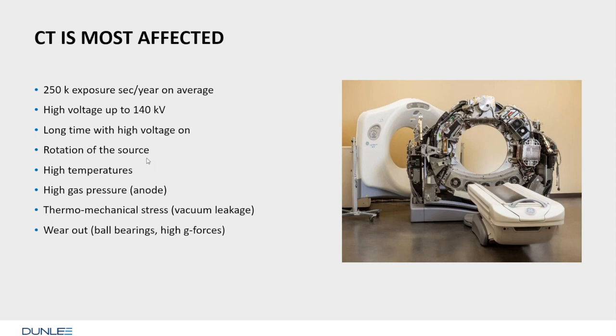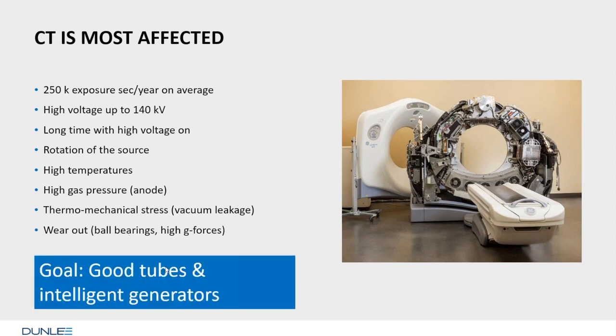We will see that. The temperatures are pretty high. CT operates some tubes to the edge. The gas pressure created by the anode may be pretty high compared to other modalities. And there may be thermomechanical stress. If you operate a tube with 30, 40, 50 patients per day, it heats and cools, so there may be thermomechanical stress and even vacuum leakage that can occur. And there's wear out. Ball bearings at high G forces and the anode also, these things are wearing out and create particles. So what we need is good tubes, stable with respect to performance. And also what we need is an intelligent generator. We will come to that.